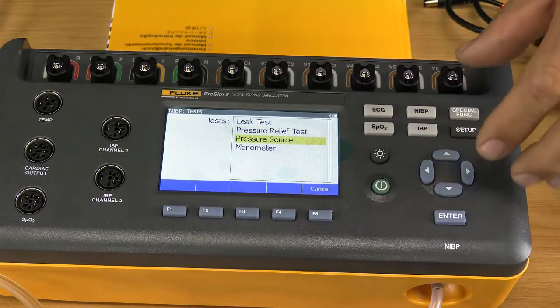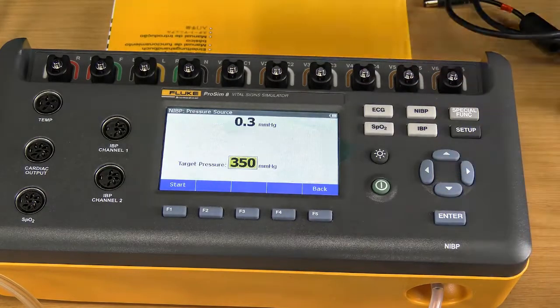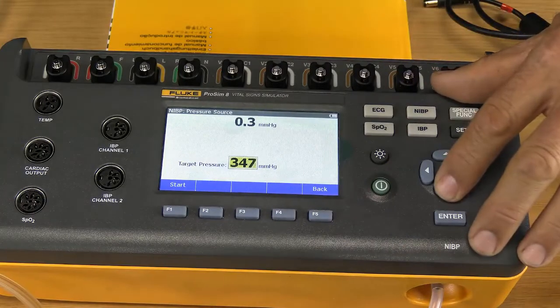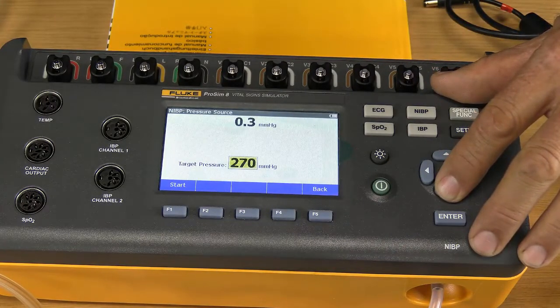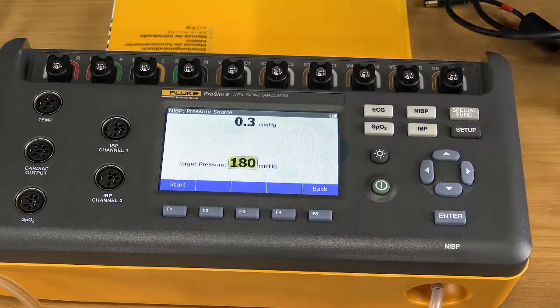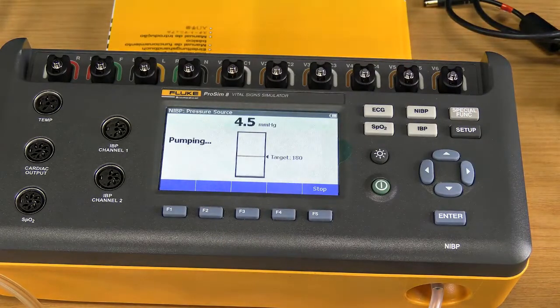Okay, let's go pressure source, enter. Pressure source is the same as the leak test we did earlier on, just with the difference that it does not have a counter. So I just want to correlate the static pressure. So I'm going to say I want the static pressure of, let's say 180. Enter, and I say start. The pump pumps up to 180, and I just correlate the two pressures with each other to see whether the machine needs calibration or not. So it's just a pressure source.